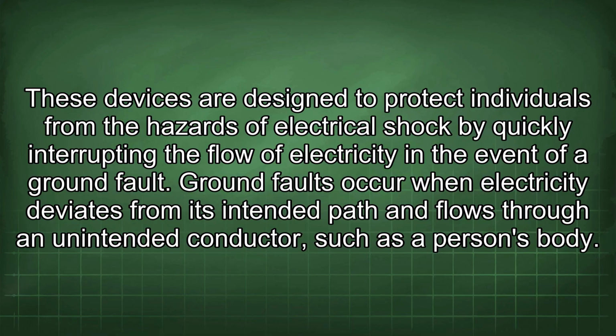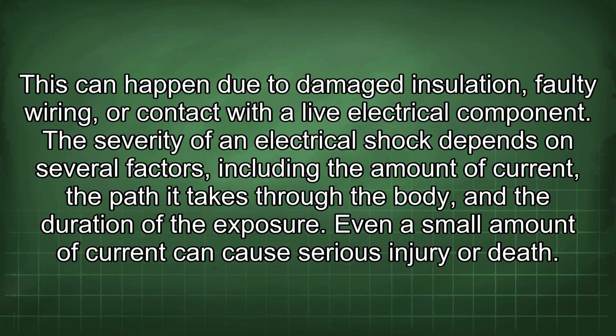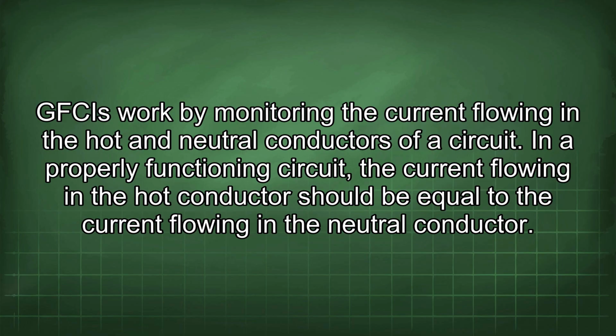Ground faults occur when electricity deviates from its intended path and flows through an unintended conductor, such as a person's body. This can happen due to damaged insulation, faulty wiring, or contact with a live electrical component. The severity of an electrical shock depends on several factors, including the amount of current, the path it takes through the body, and the duration of the exposure. Even a small amount of current can cause serious injury or death. GFCIs work by monitoring the current flowing in the hot and neutral conductors of a circuit. In a properly functioning circuit, the current flowing in the hot conductor should be equal to the current flowing in the neutral conductor.